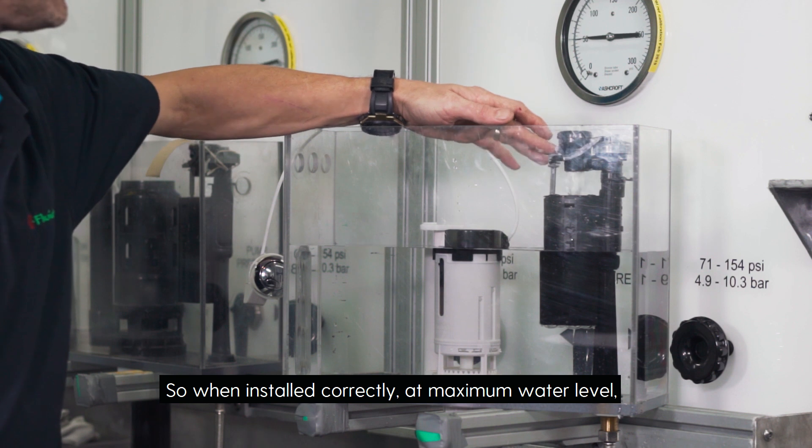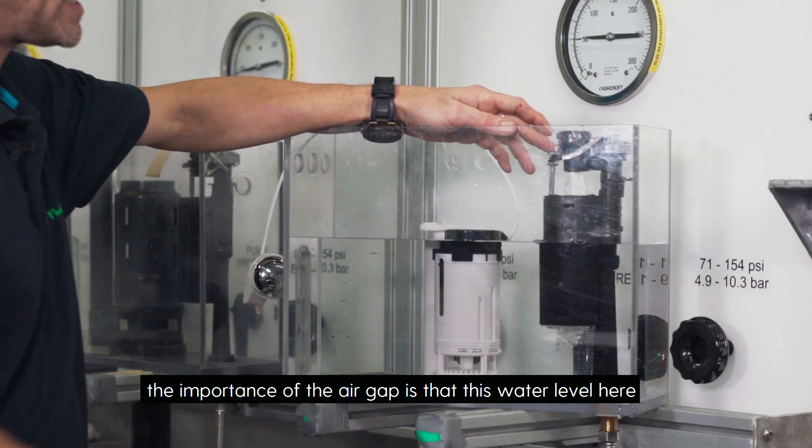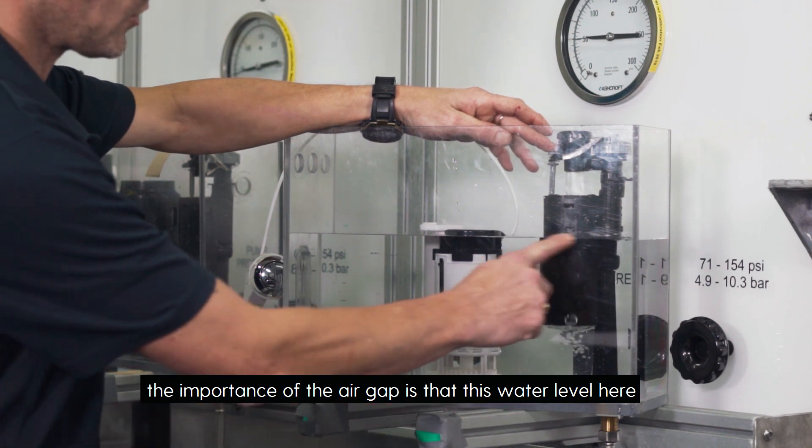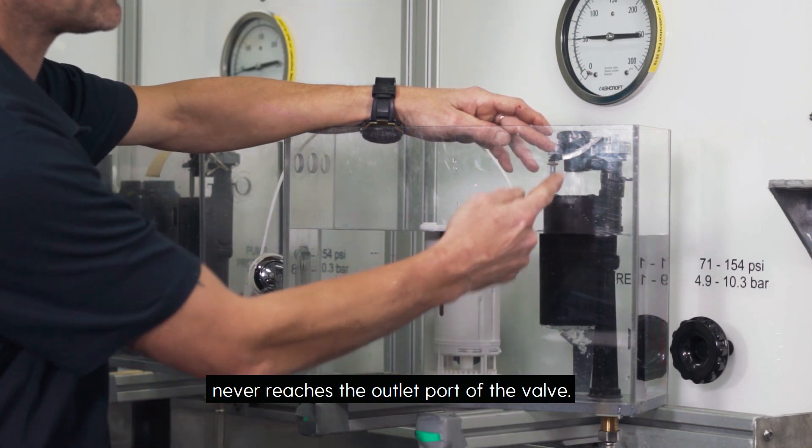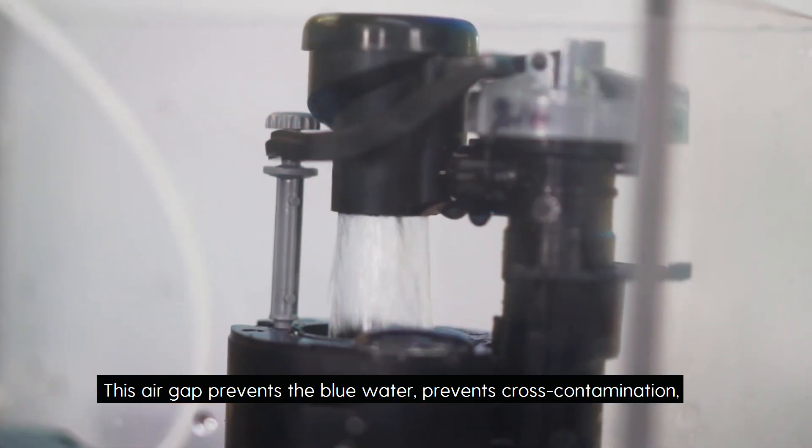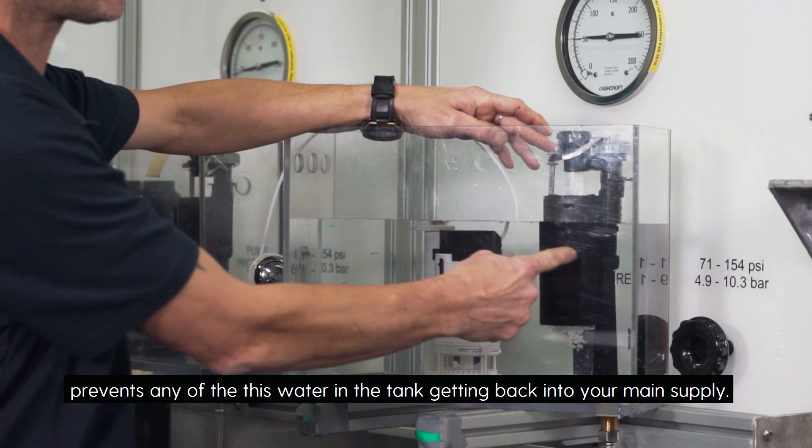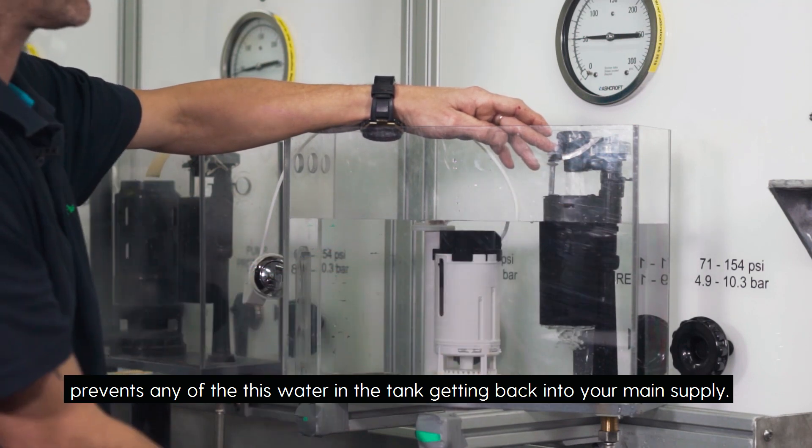When installed correctly at maximum water level, the importance of the air gap is that this water level never reaches the outlet port of the valve. This air gap prevents cross contamination and prevents any of this water within the tank getting back into your main supply.